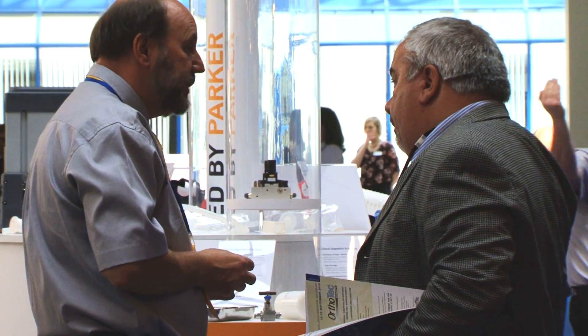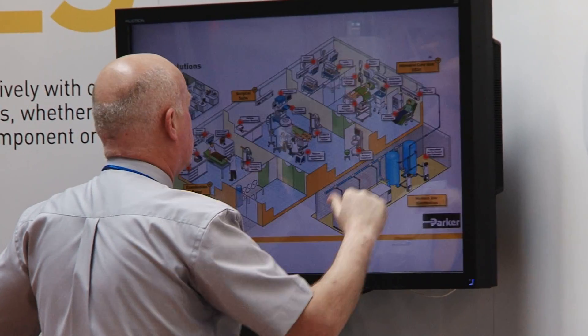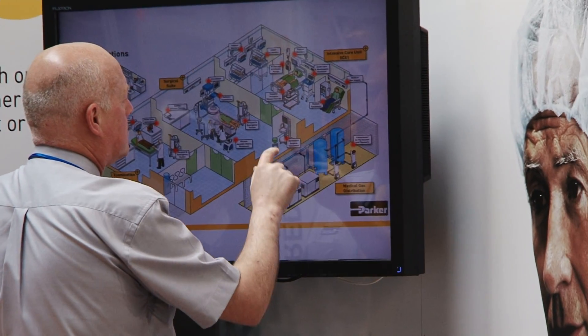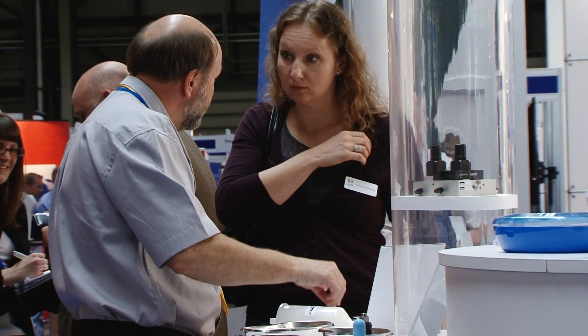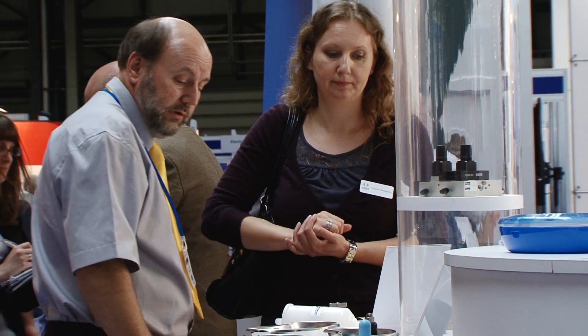The Parker KV division is just one of the divisions that we are representing here today, and they work as a collaborative partner in designing bespoke solutions for the life science original equipment manufacturers. One such example is the gas alarm module for an anaesthesia machine. The gas alarm module has two primary functions — the first provides an audible alarm when the master gas pressure drops.